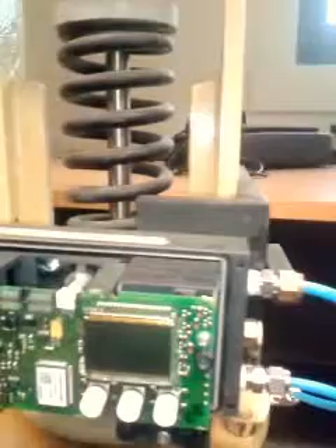By the way, here is a control valve. When we calibrate the positioner, we attach the positioner here and then try to actuate this valve. This is a linear valve, globe valve. This is a Siemens Sipart PS2 model valve positioner, but this is defective.